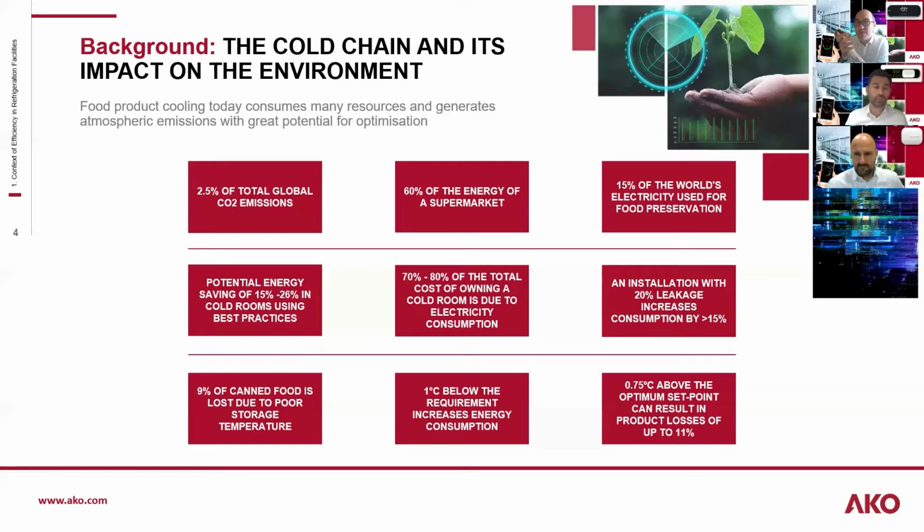Also, it's important to know that it's not only about energy consumption, but also factors like the leakage of gases that affect the installation's optimization. Just to give you an idea, 20% of leakage in your installation increases the consumption by 15%, and this is completely exponential. The more you leak, the more you increase your consumption exponentially.